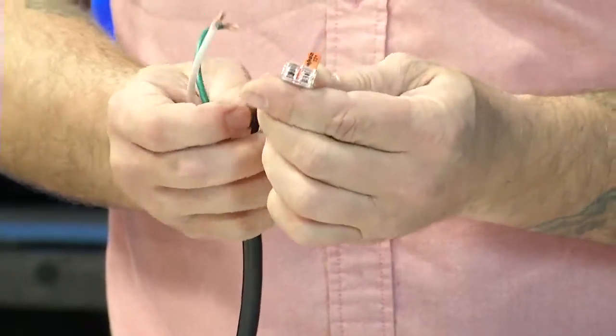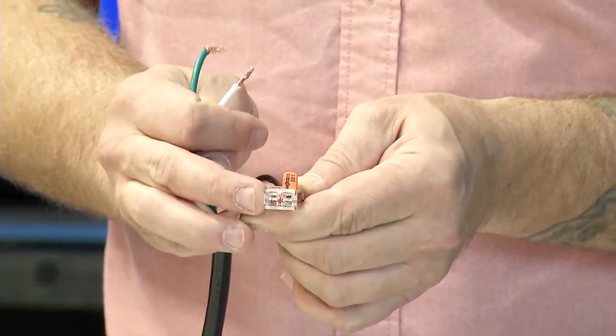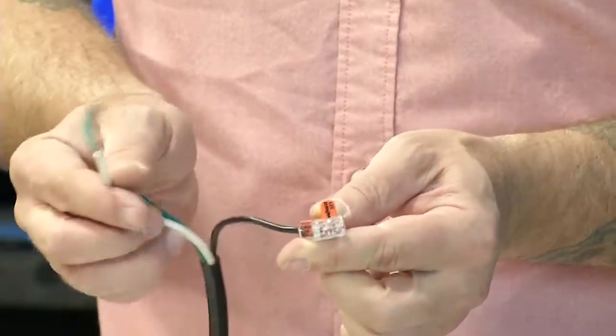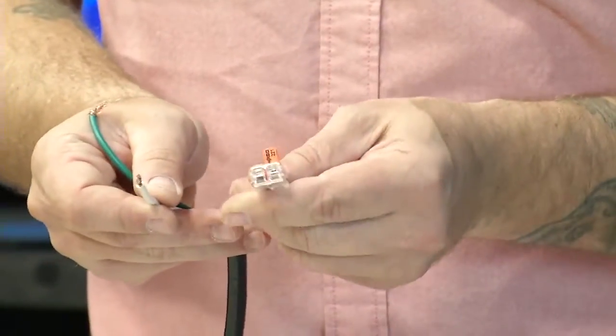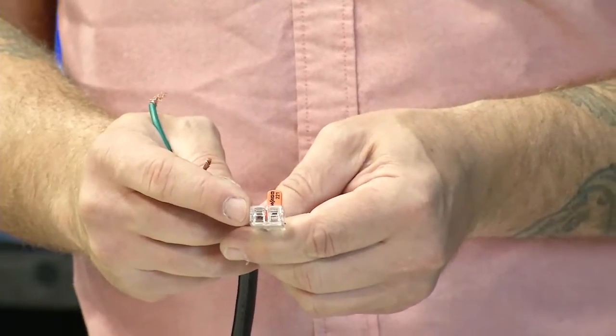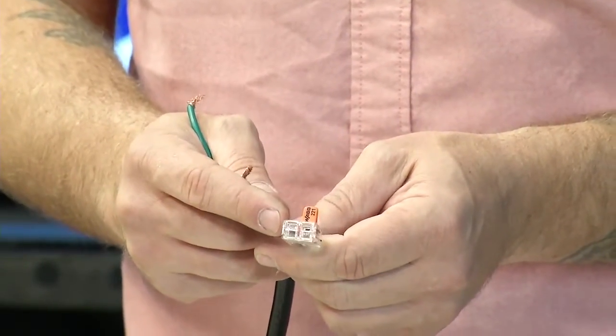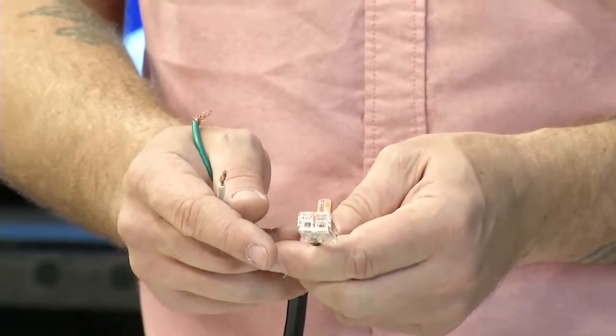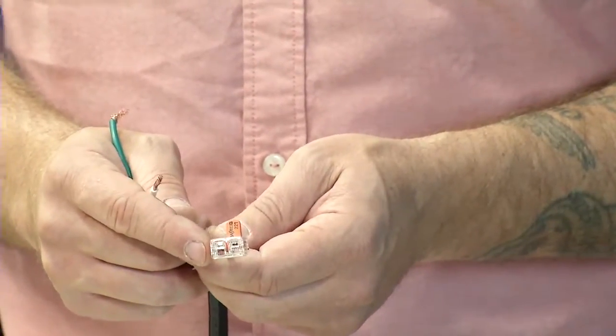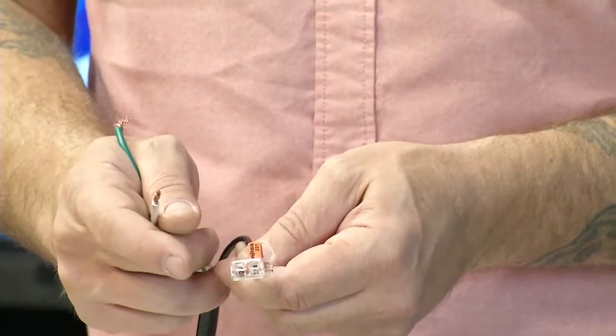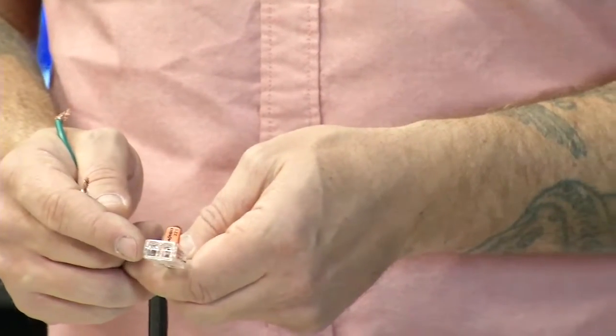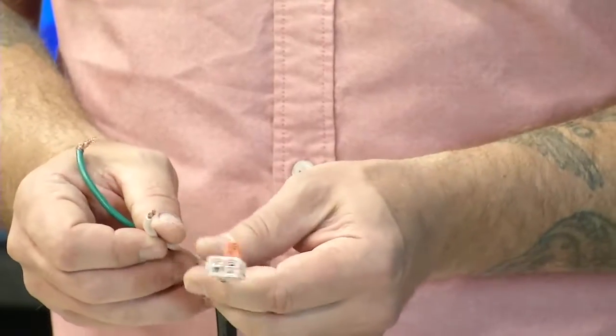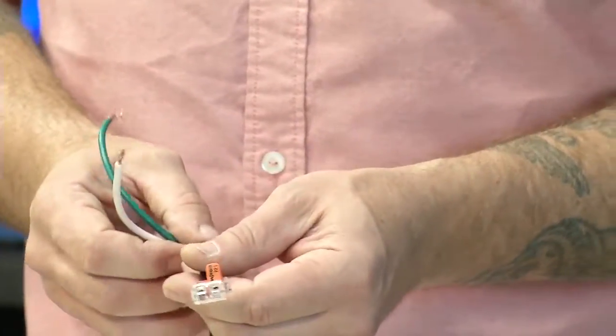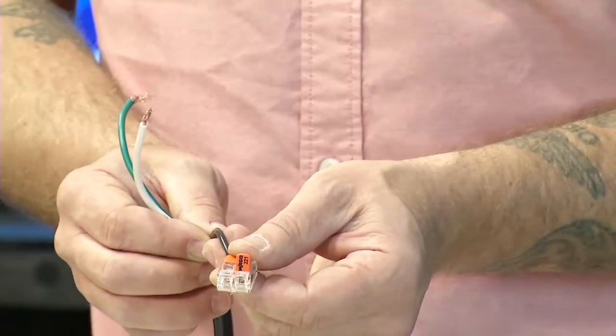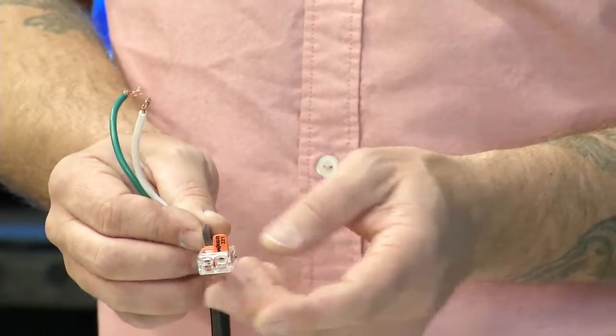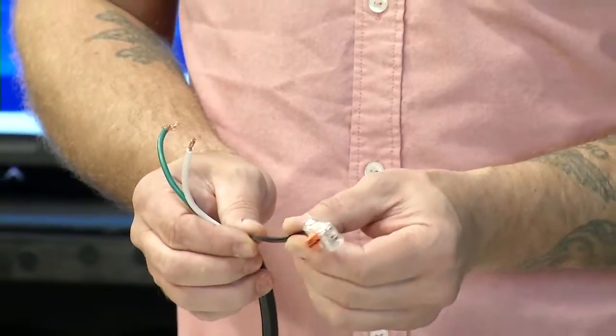You won't be able to see it, but on the back side there's a little opening—if you had your hot black wire and your negative hooked up, you can actually put your voltmeter on the back side. There's an opening where you can test without pulling the wires out, so you eliminate a lot of wasted time getting connections off and putting them back on, just by putting your prongs on the back of a WAGO to test your voltage between connections. WAGO is something we're starting to use on some of our products, and a lot of the OEMs are using it as well.